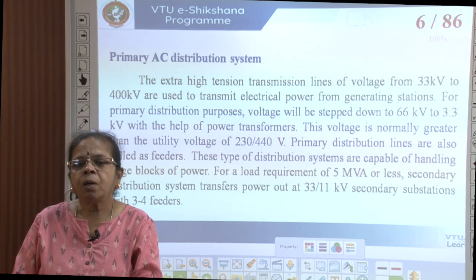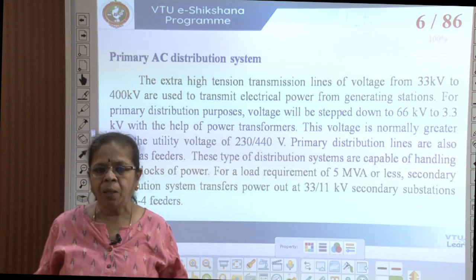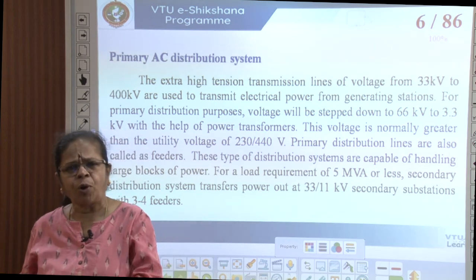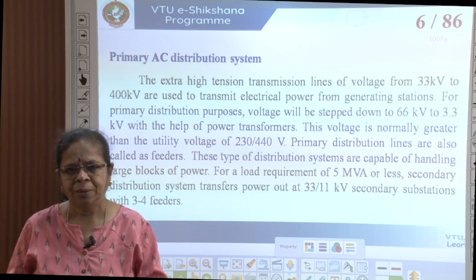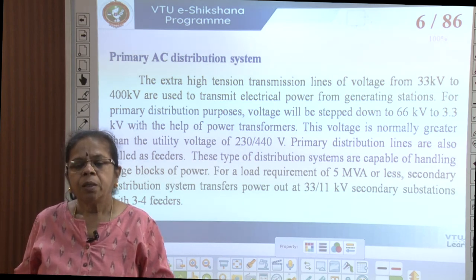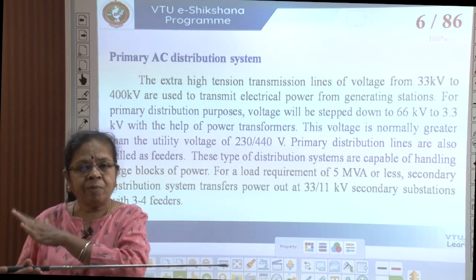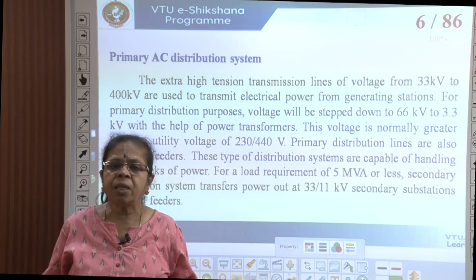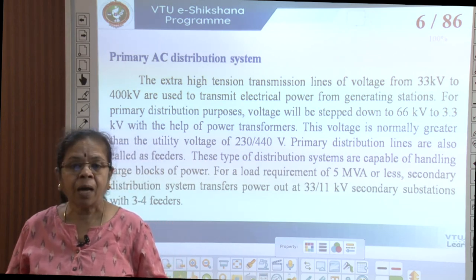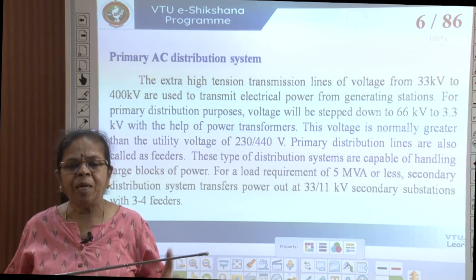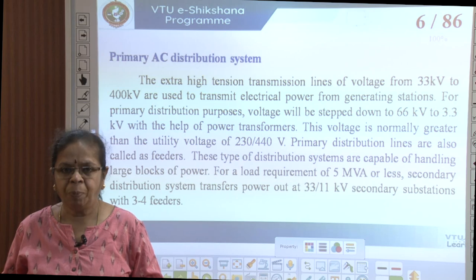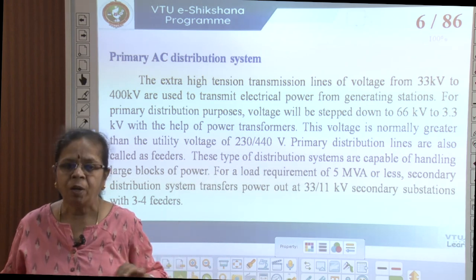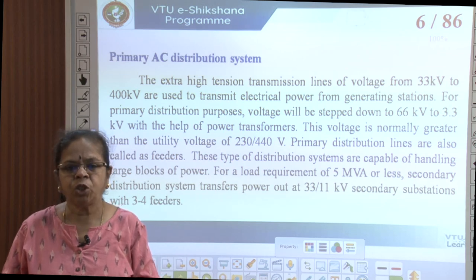At the lowest consumer level, I need between 230 to 440 volts. Sometimes we say 400 volts, 415 volts, or 440 volts — it is a range of voltages permitted. The primary distribution lines are called feeders. Feeders are conductors where there is no tapping in between. From the feeder, power is given to different distributors. Feeders normally carry bulk power from the substation to a local point.